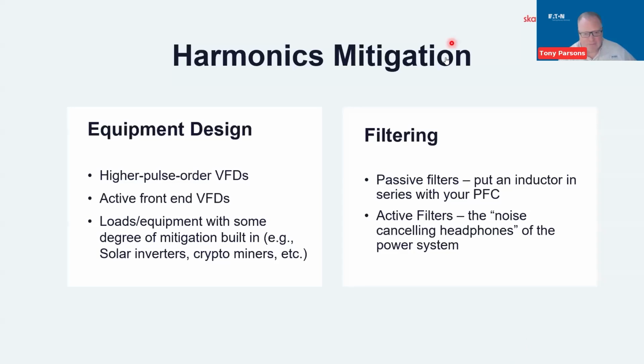One of the newer developments, becoming more and more common in recent years, is active front end VFDs doing much the same thing, or loads or equipment that have some degree of mitigation built in. Solar inverters, crypto miners, the folks out there trying to get the Bitcoin or whatever. Sometimes installations with a great deal of load, and if the manufacturers of those devices weren't trying to take harmonics into account, they really would be causing some problems for the system. Now, all of those things, they're electronic loads. They have components that are switching sometimes at very high frequencies. Steve is going to, in the next section, talk about the effect of some of those things that you see sometimes, the super harmonics that can cause other types of issues.